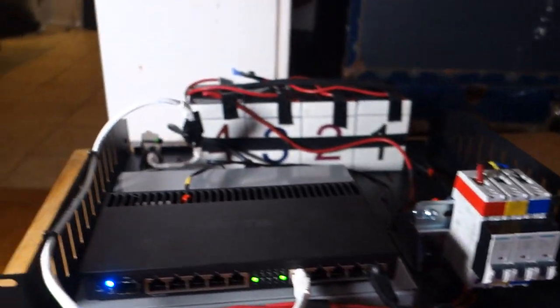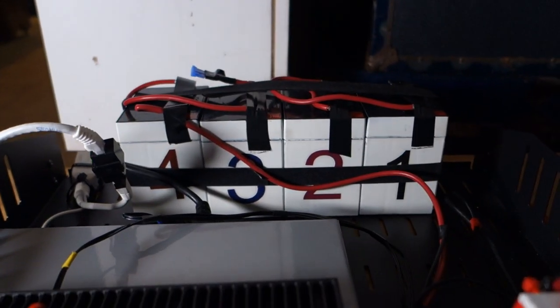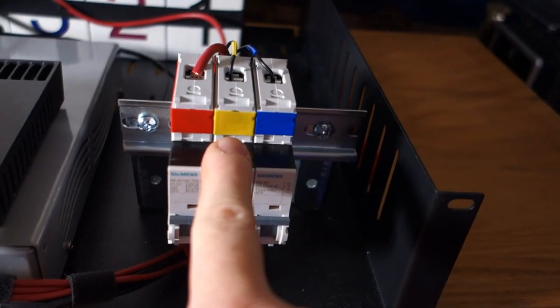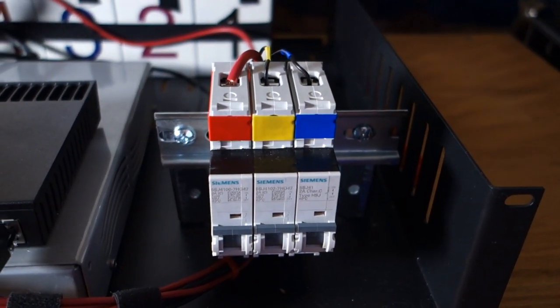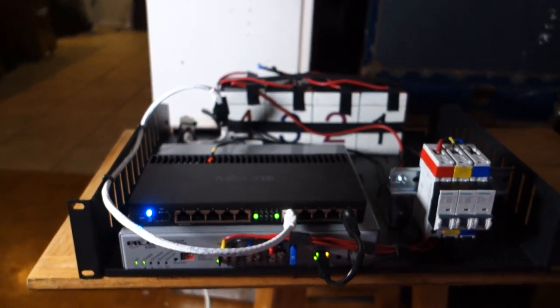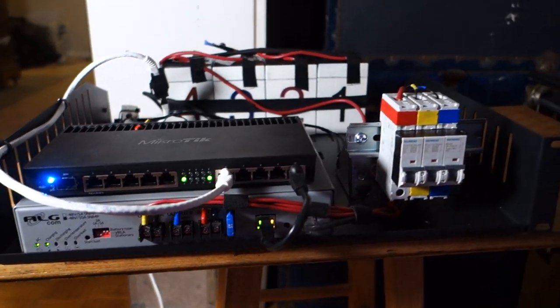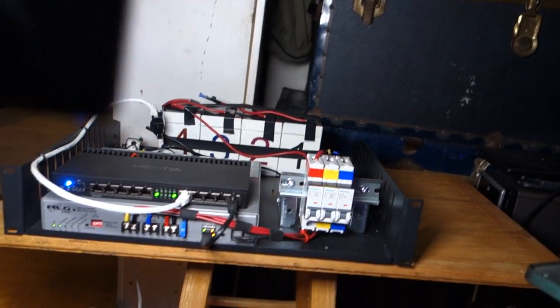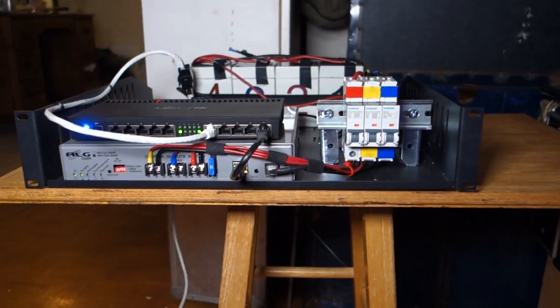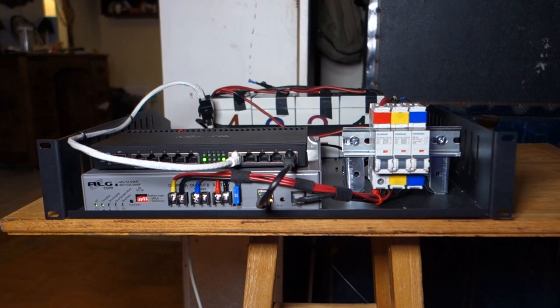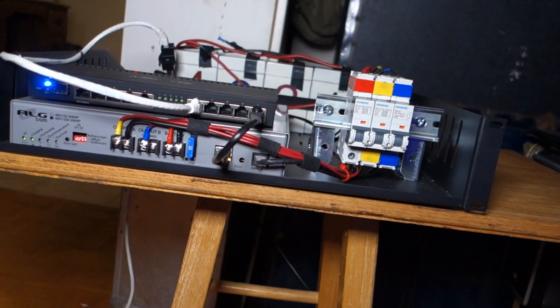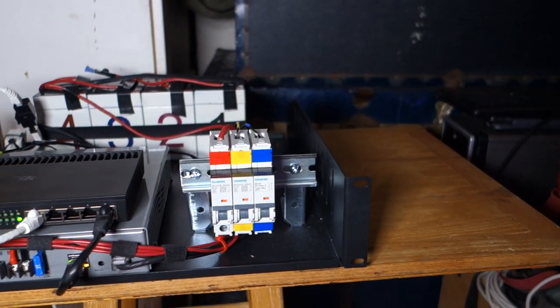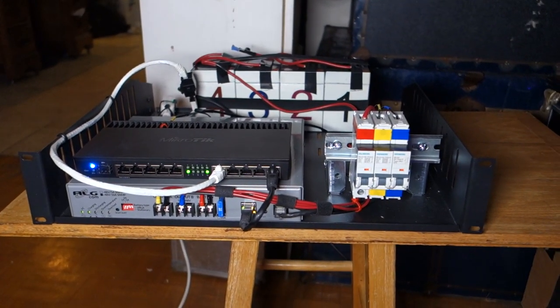That's basically what we're doing here. We've got our power supply for the whole plant, one cable, 48 volts at say four and a half amp hour. We've got our breakers here, battery breaker, router breaker, and outdoor enclosure breaker. That's basically everything that we're doing here, and it's mounted all within a 2U shelf. The reason why it's mounted in a 2U shelf is because the tower owner was kind enough to let us use one of their racks at their site. They said you guys can use some rack space, just mount it in there. I could have just eared and eared and put it on the rack, but then I needed the shelf for the batteries anyway, and I need a spot for the breakers anyway. So to keep it tidy and put it together, this is yet another option.